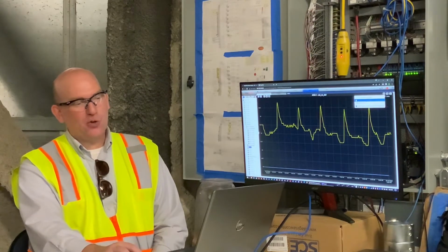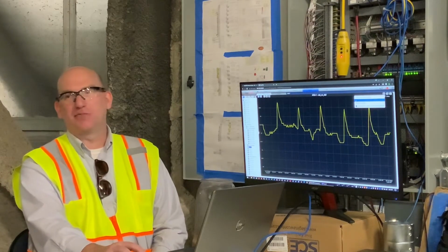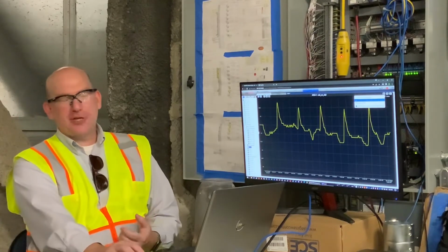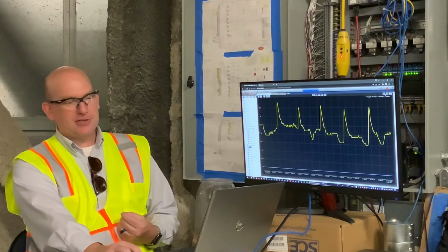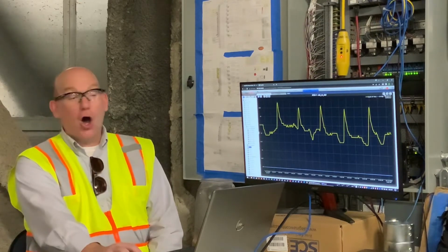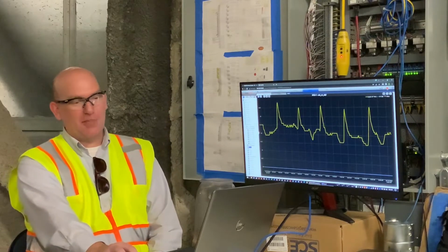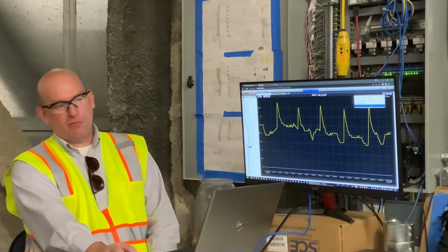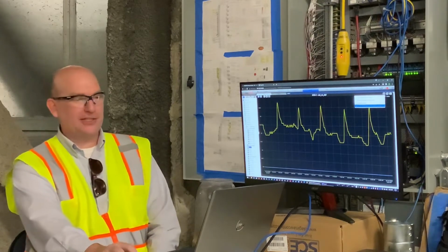Show database values only kind of takes anything out of the graphic that hasn't been logged at the server. So we store a lot of our trend information right in the controller, and then periodically dump it to the server. If you only for some reason wanted to see what was in the server and not in the controller, check that box, and it'll only show you what's in the server. Do they stay there? No, anytime you go somewhere else and come back, those options are, you got it. This one here is always checked for adding in spots where there might be missing data, but the other three always default back to being on.